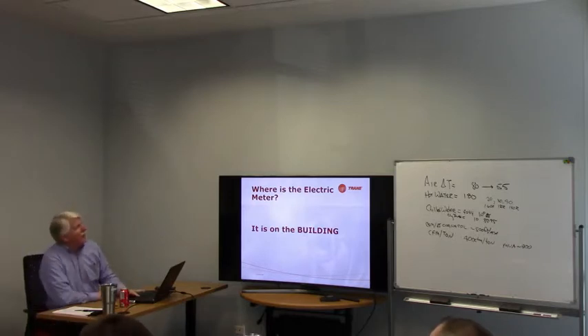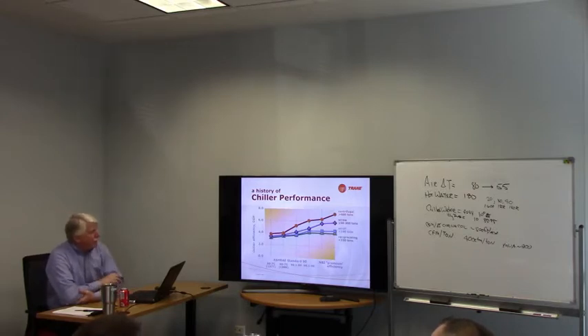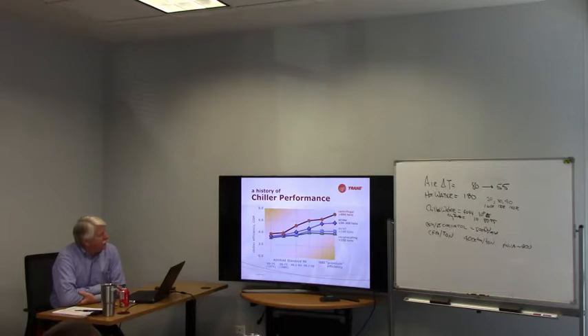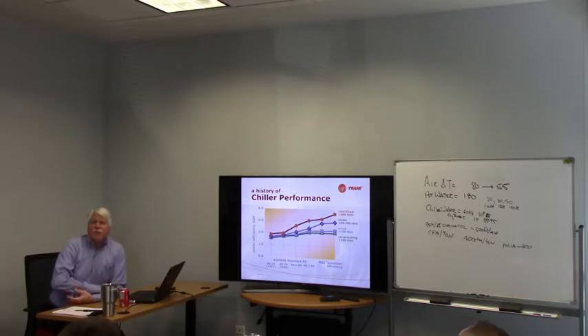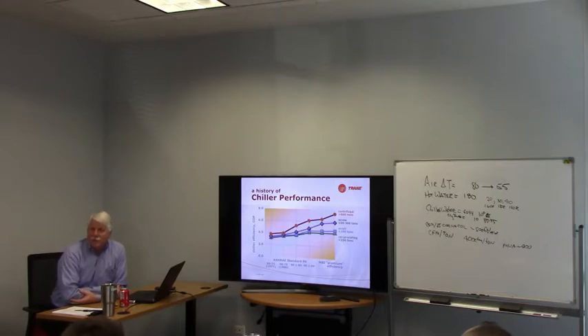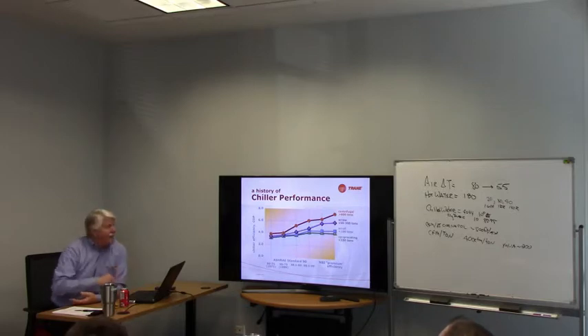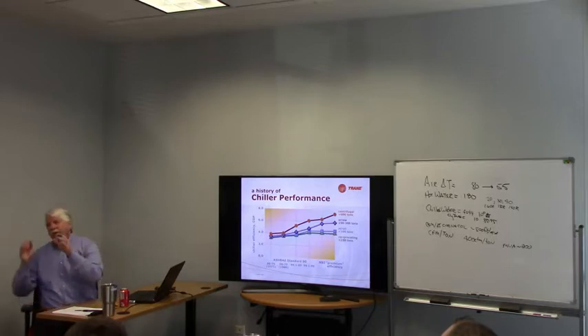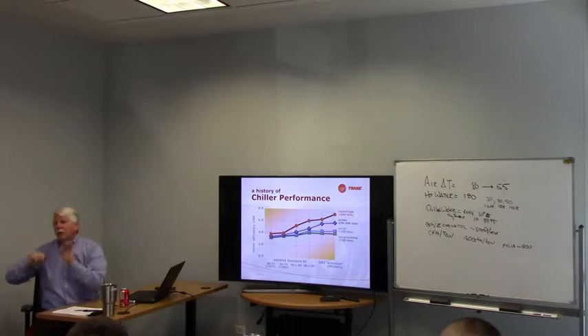So this focuses on how we can try to save some money. This is a real interesting thing. It's called the chiller COP, the coefficient of performance, which is a function of chiller efficiency. And back in 1977, you were hard pressed to get a 4 COP. Now we're up on some of them over 6.5, okay? And how did we get our efficiencies on our chillers up so dramatically? The main thing is the tubes. Back in 1977, the tubes in both the evaporators and the condensers were smooth bore tubes, and the external side of them was smooth also.